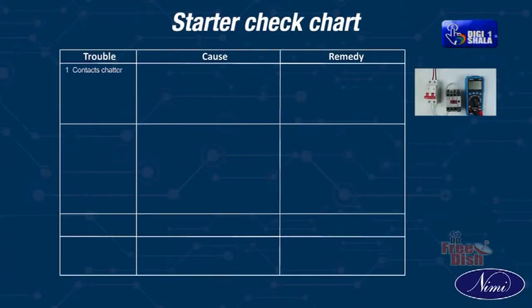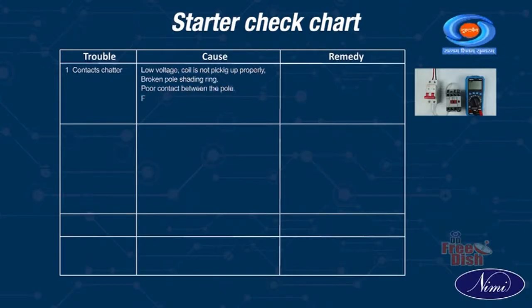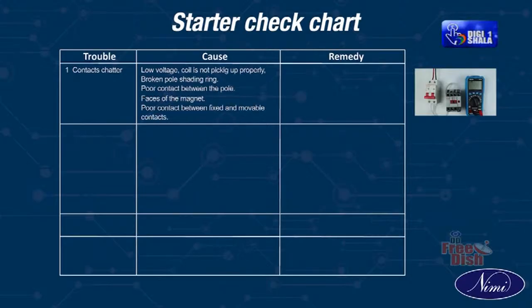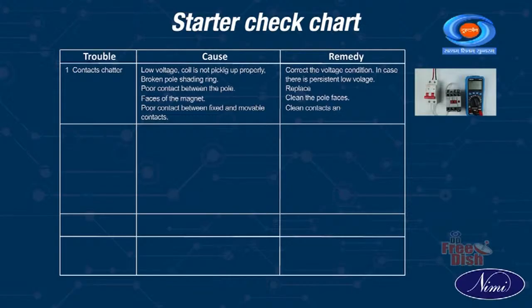Number 1. Contacts chatter. Cause. Low voltage, coil is not picking up properly. Broken pole shading ring. Poor contact between the pole faces of the magnet. Poor contact between fixed and movable contacts. Remedy. Correct the voltage condition. In case there is persistent low voltage, replace. Clean the pole faces, clean contacts and adjust if necessary.